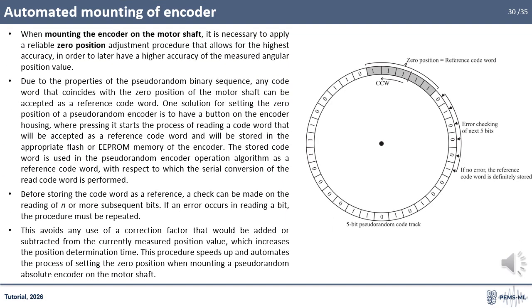When mounting the encoder on the motor shaft, it is necessary to apply a reliable zero position adjustment procedure that allows for the highest accuracy in order to later have a higher accuracy of the measured angular position value. Due to the properties of the pseudorandom binary sequence, any code word that coincides with the zero position of the motor shaft can be accepted as a reference code word.